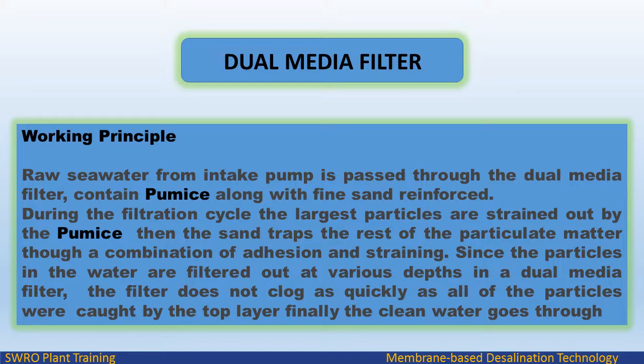Raw seawater from the intake pump is passed through the dual media filter, which contains pumice along with fine sand. During the filtration cycle, the largest particles are strained out by the pumice, then the sand traps the rest of the particulate matter through a combination of adhesion and straining. Since particles are filtered at various depths in a dual media filter, the filter does not clog as quickly as if all particles were caught by the top layer. Finally, the clean water passes through.